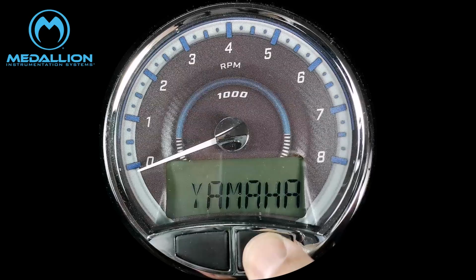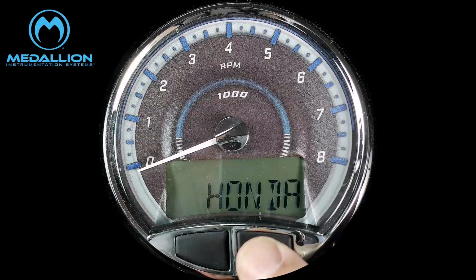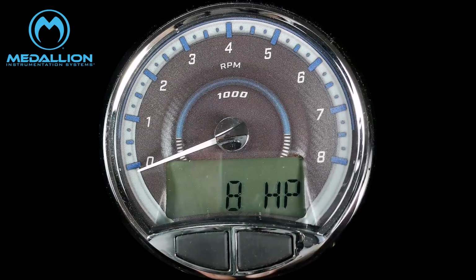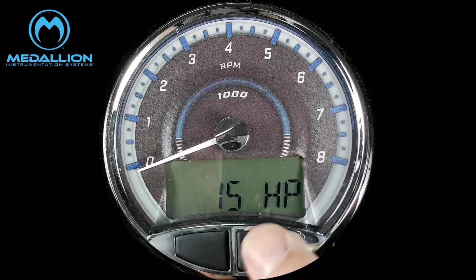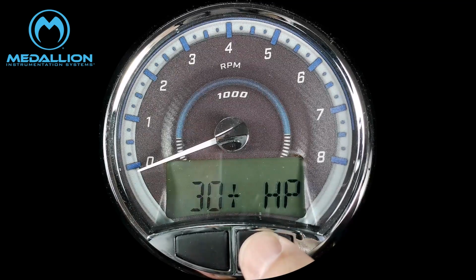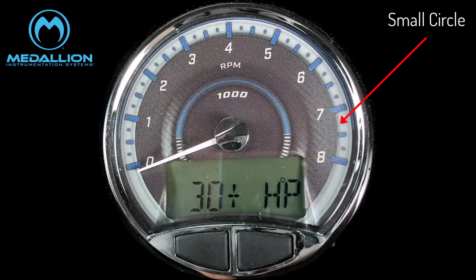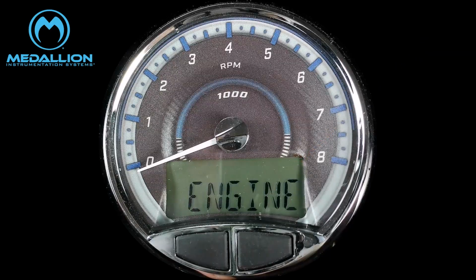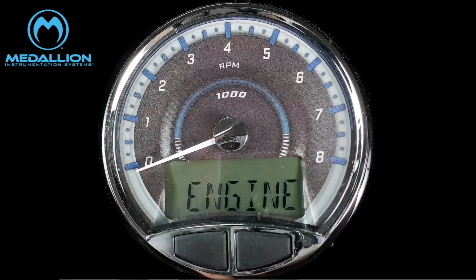Let's say that we want to program the Honda engine. When we see Honda on the display, then press the button for approximately 1 second. Now the type of Honda engines will be displayed. Simply press either button until the correct engine type is displayed. Now press the right button for approximately 1 second, or until the dot is displayed. This indicates that this engine type is now programmed for the gauge. After approximately 2 seconds, the gauge will exit the engine mode.